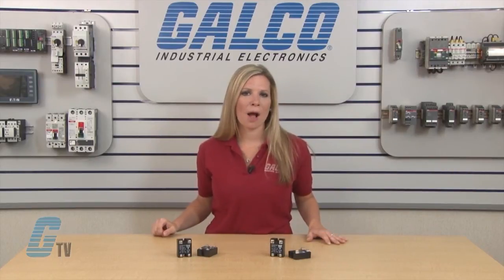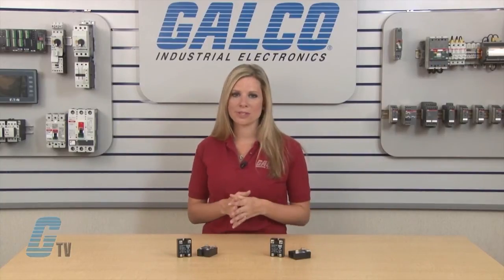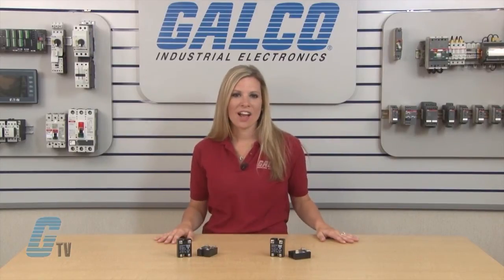The system monitoring relays, or sense relays, have an alarm output in case of circuit failure. They can monitor the line voltage and current as well as input status and functioning of the solid state relay. They are ideal for applications where immediate fault detection is required.